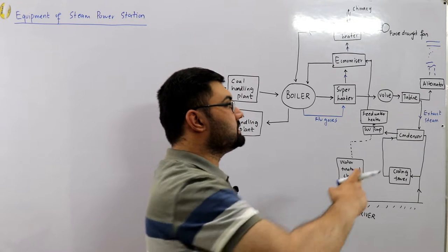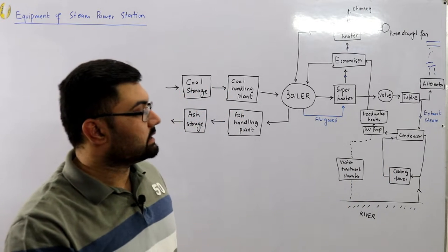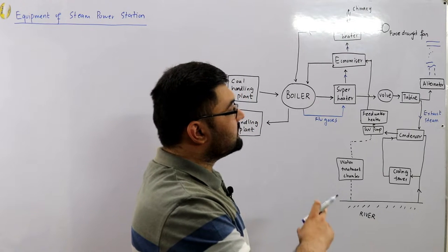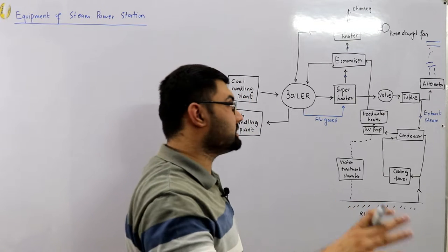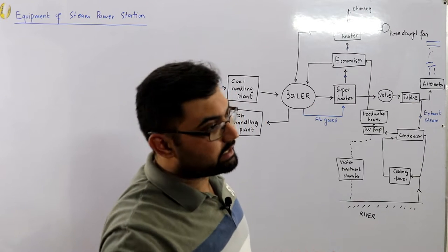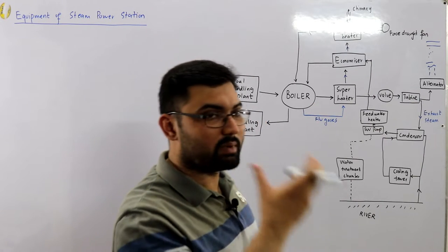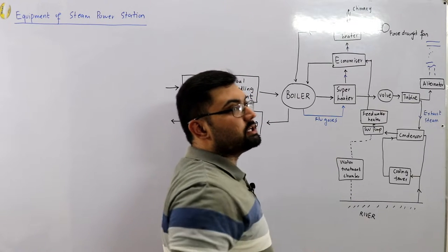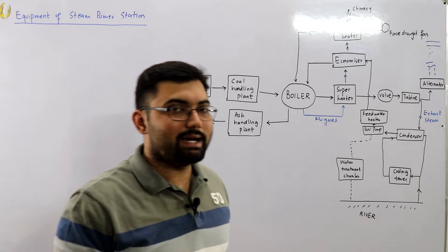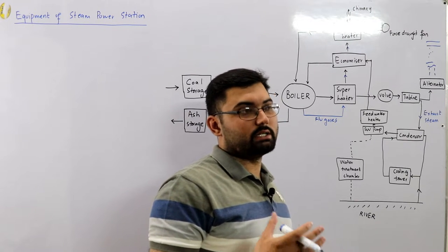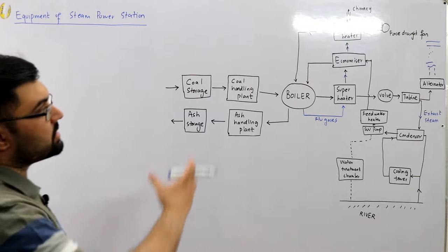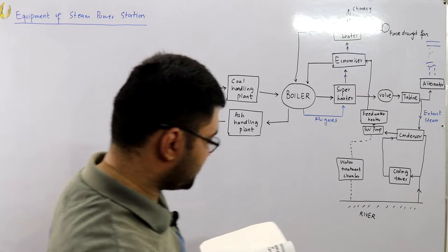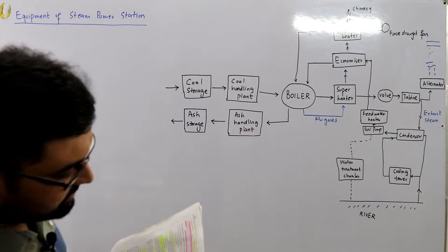A valve regulates the flow of steam to the turbine. The exhausted steam goes to the condenser where it is condensed back to water. The river provides makeup water for losses. The condensed water, called feed water, is fed back through the economizer via the feed water pump. A feed water heater is also on the way. A water treatment chamber removes impurities, dissolved gases, and marine life. A forced draft fan provides the air required for the combustion process.